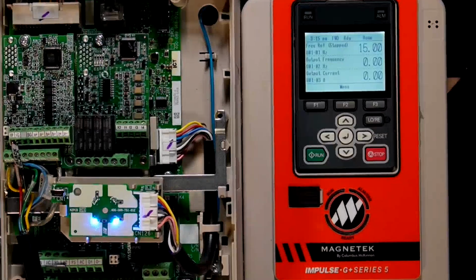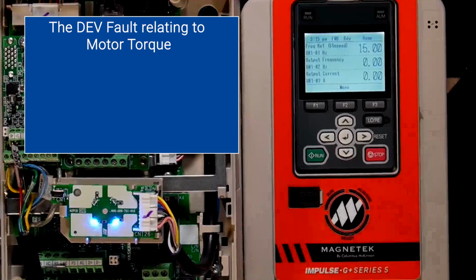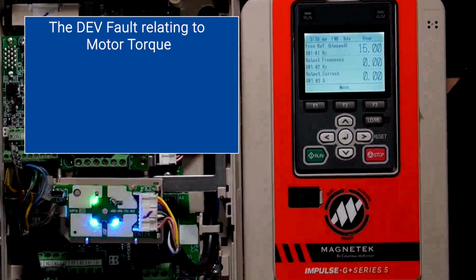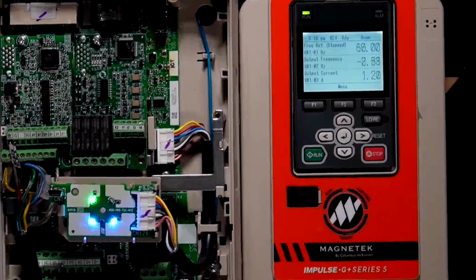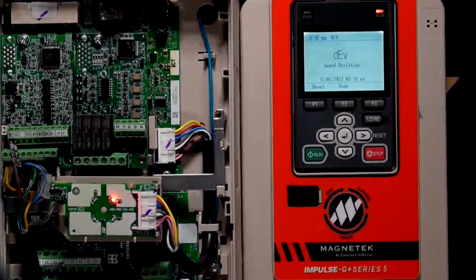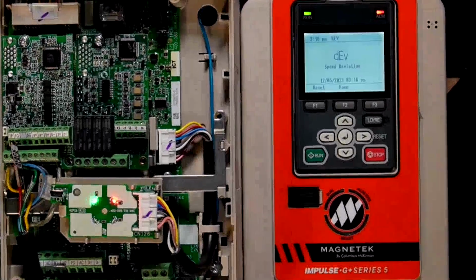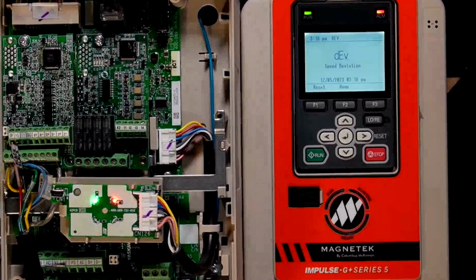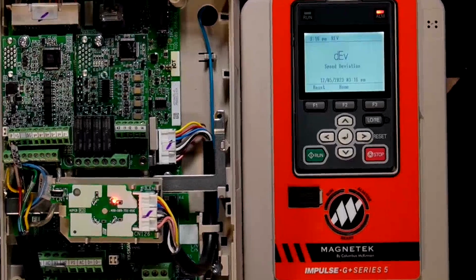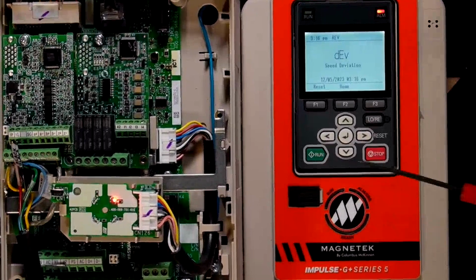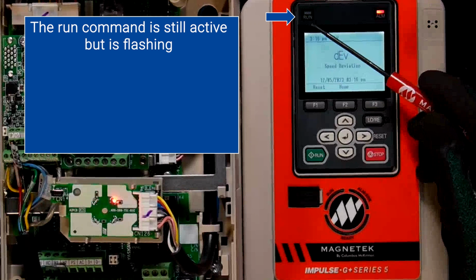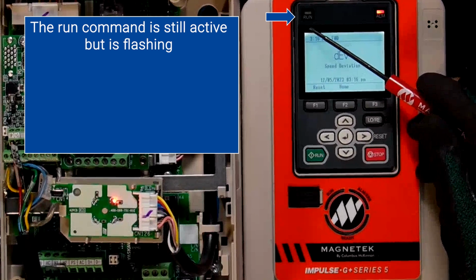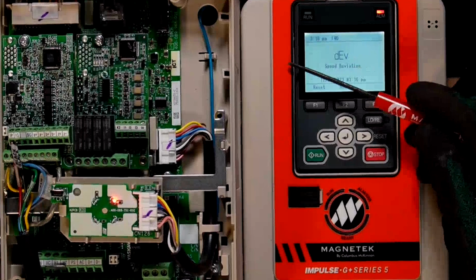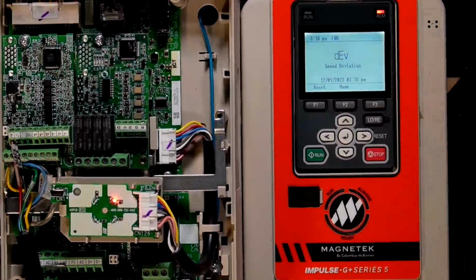Now the next thing I'm going to demonstrate is the DEV fault related to motor torque. So I'm going to give the drive a run command. And I've held on to the flywheel on the motor. And if you notice, the drive is locked into a DEV fault. Now it's important to note that right now I still have the run command active on the drive and the run light is flashing. I'm going to release the run command. That means I've released the run command, but the drive is still locked in the DEV fault.